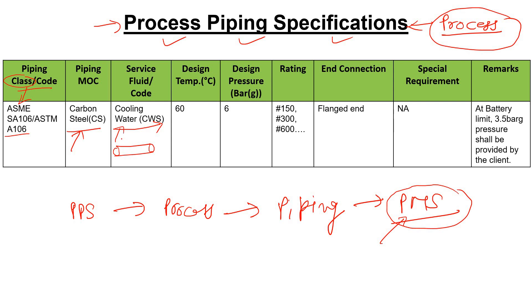What will be the design temperature of this cooling water supply line? The design temperature will be 60 degrees Celsius. The operating temperature of cooling water is typically around 30 to 38 degrees Celsius, which is why the design temperature is set at 60. Sometimes you will see maximum operating temperature used instead. Similarly, the design pressure is 6 bar, while the typical operating pressure in cooling water lines is 3.5 bar.